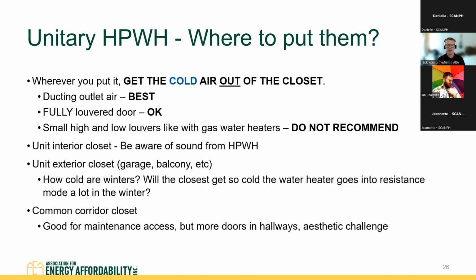You don't need to necessarily duct it all the way outside. These aren't generating so much cold air that if you dump it into the apartment, you're going to make the whole apartment freezing cold. It's not that insane. In fact, there have been studies that show it has no real noticeable impact on heating or cooling loads inside the apartment. There's a slight cooling benefit to having a heat pump water heater inside, but it's not a huge impact. You just want to get the cold air out of the closet. That's the main thing. So just get it out of the closet and you're okay.